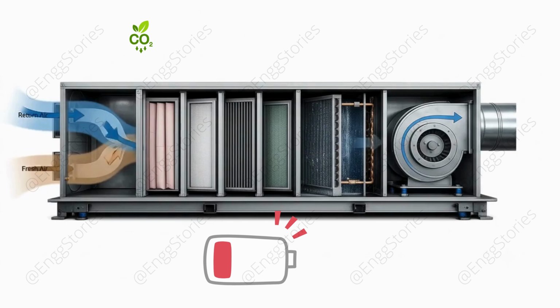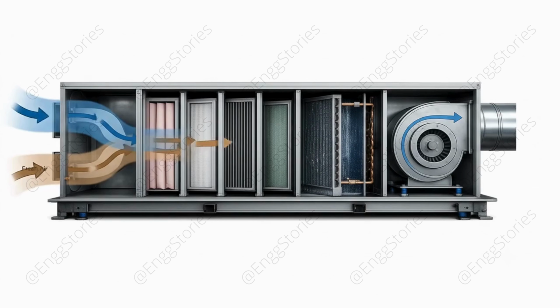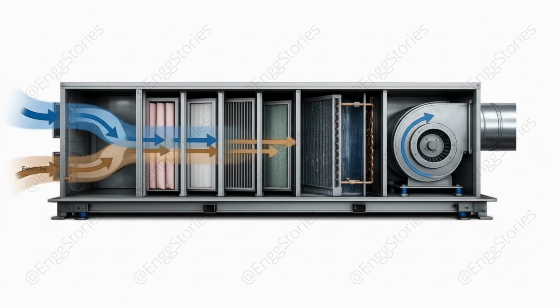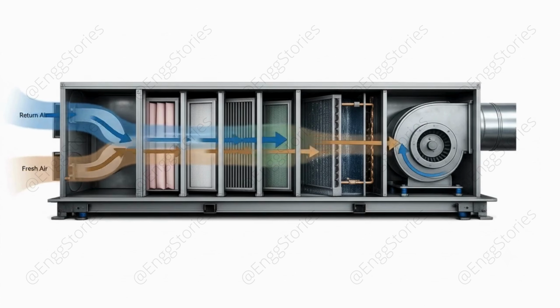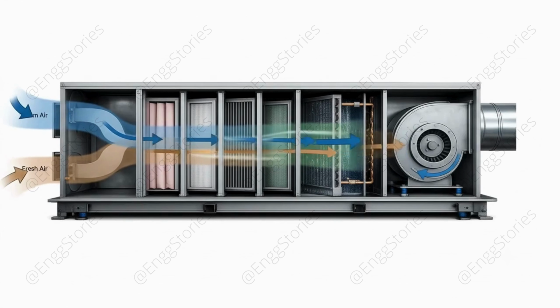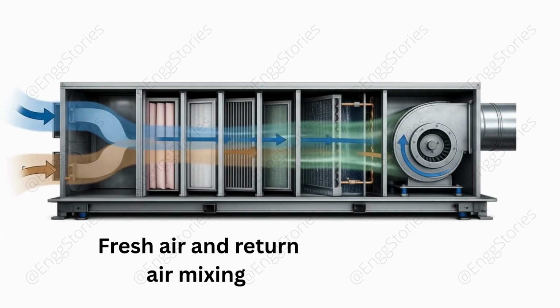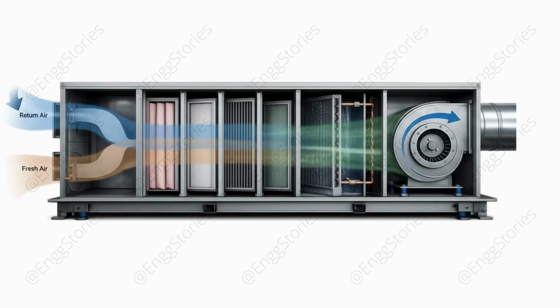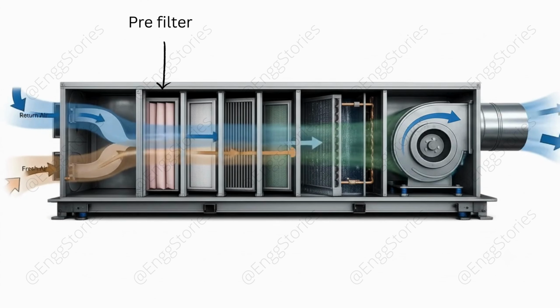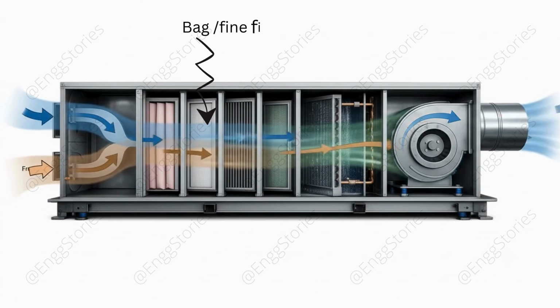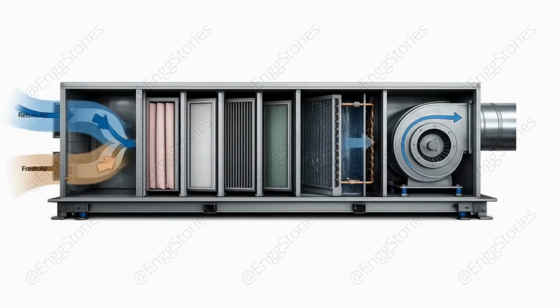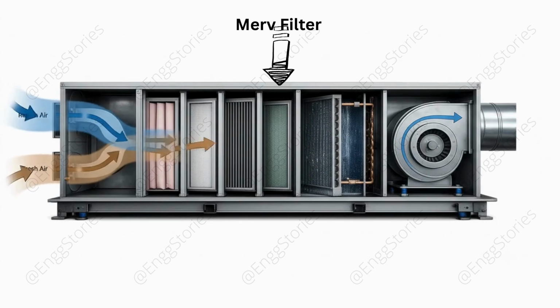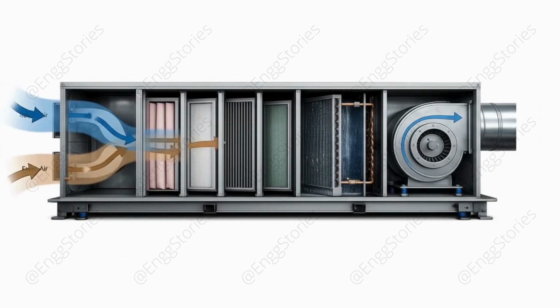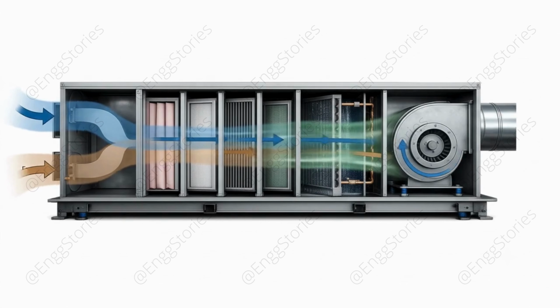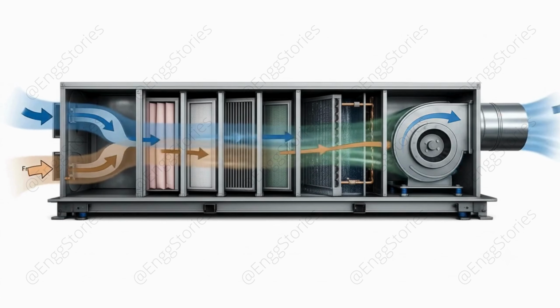That's why the AHU uses fresh air dampers and return air dampers. These dampers control how much fresh air and return air enter the AHU, maintaining good indoor air quality while also saving energy. Once inside the AHU, the fresh air and return air mix together. Since the fresh air coming from outside may contain dust, pollen, and other airborne particles, the mixed air first passes through a series of filters. It typically flows through a pre-filter, which removes larger dust particles. Then it passes through a bag filter or fine filter to capture smaller particles. In many systems, a MERV-rated filter provides even finer filtration, ensuring the air is clean before it reaches the cooling coil. After passing through all these filters, the clean air finally reaches the cooling coil, where it is cooled and supplied to the rooms through the duct system.